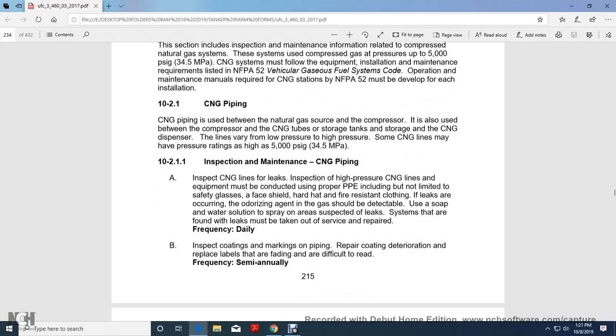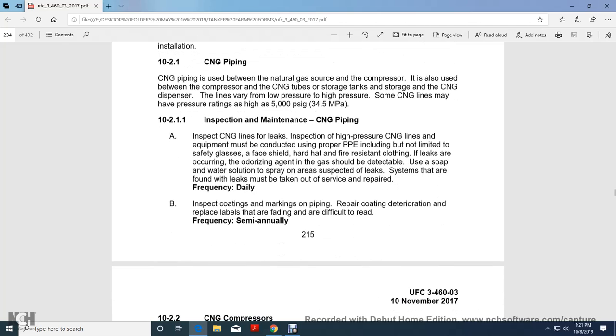Compressed Natural Gas Piping. CNG piping is used between the natural gas source and compressor, between the compressor and CNG storage tubes and tanks, and between storage and the CNG dispenser. Lines vary between low pressure and high pressure CNG lines, with a pressure rating of up to 5,000 psi gauge. Inspection and maintenance: inspect CNG lines for leaks. Inspection of high pressure compressor and CNG lines must be conducted with proper personal protective equipment including safety glasses, face shield, hard hat, and fire-resistant clothing. If leaks are occurring, the odorizing agent in the gas should be detectable using a soap and water solution on suspected areas. Leaks must be taken out of service and repaired daily. Inspect coatings and markings of the pipe; repair deteriorated coatings and replace labels that are fading or difficult to read. Frequency: semi-annually.